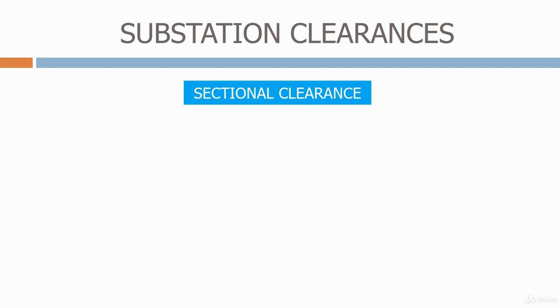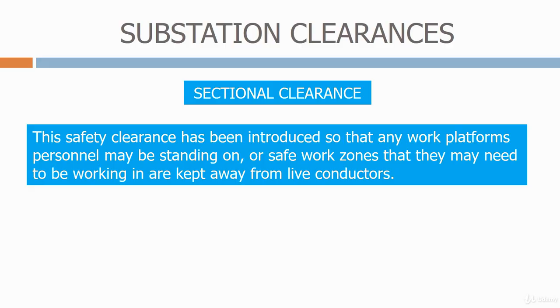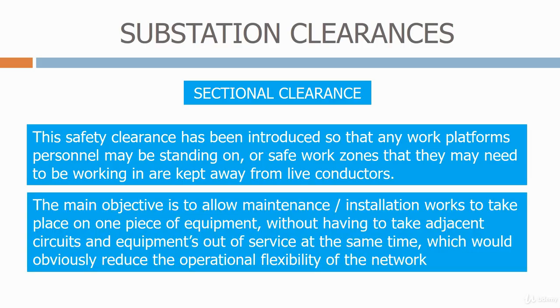Finally, we have the sectional clearance. This safety clearance has been introduced so that any work platforms personnel may be standing on, or safe work zones that they may need to be working in, are kept away from live conductors. The main objective is to allow maintenance or installation works to take place on one piece of equipment without having to take adjacent circuits and equipment out of service at the same time, which would obviously reduce the operational flexibility of the network.